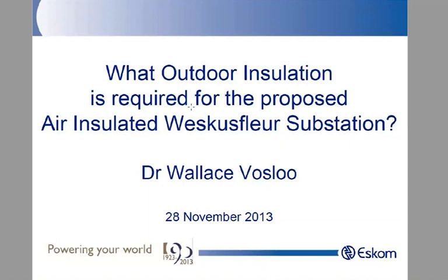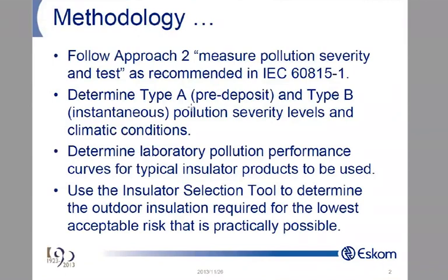Now we need to build a new substation there, obviously, and for this substation, we need to do the design, and we want this substation's insulation optimally selected, okay? And then the guys came up with a ridiculous figure of how many years between flashovers. So here I am, and I need to choose a methodology. So I said I'll follow approach 2, where I measure the pollution in the area and the climate. I do a test in the lab, I come back, and now I calculate risks and try and select my insulation in such a way that I can reduce my risks to 1 flashover in gazonks years, okay.